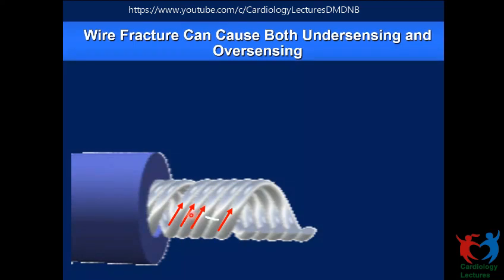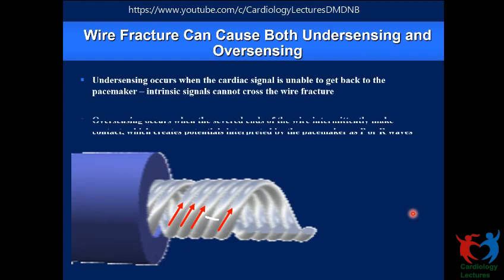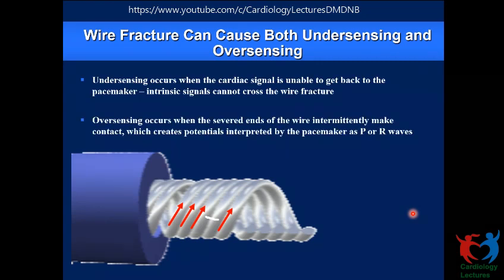Of course, if there is a serious enough fracture, as we said, by application of Ohm's law, the pacing stimulus that is delivered at the tip will become significantly smaller, lower than the threshold, and that might not capture. So both oversensing and loss of capture can happen when there is a fracture. Of course, there will be an impedance change. You will detect it based on that. So both wire fracture and insulation breaks can cause oversensing as well as undersensing.